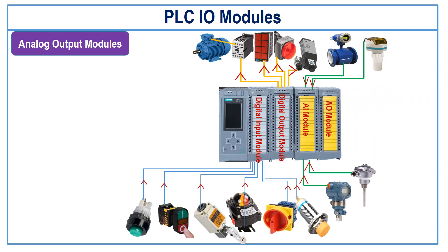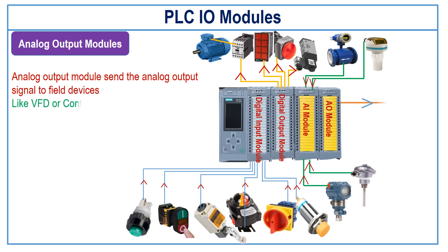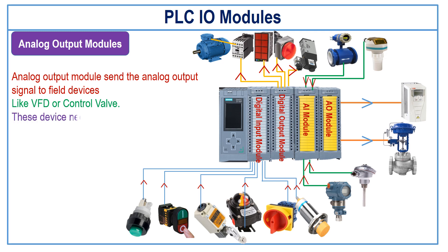Analog output module: The analog output module sends a continuous analog output signal to the field devices like VFD or control valve. These devices need an analog signal to operate. If you have to control the opening of a control valve, you can control it by giving a 4 to 20 mA analog signal from the analog output module. If the output is 4 mA, the valve will be in fully closed condition, and if the analog output is 20 mA, then the valve will be 100% open. The valve's opening can be controlled anywhere between 0 to 100% by giving the appropriate analog output signal from the analog output module.